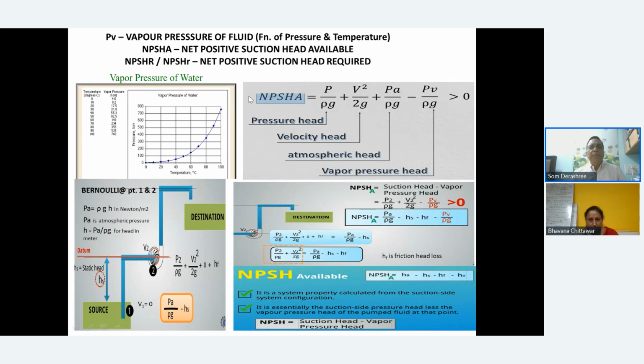Now, what is NPSH? Basically, there are 3 or 4 terminologies. But before you understand NPSH, let us first understand that each liquid has a vapor pressure. If you see this chart here, all liquids follow this characteristic: as the temperature increases, vapor pressure also increases. The same goes when the pressure reduces, the vaporization point changes. The liquid will boil much faster if you go to the Himalayas than when you are at Chennai, because the atmospheric pressure is lower at height. So the boiling point will be higher in Chennai and lower in the Himalayas.